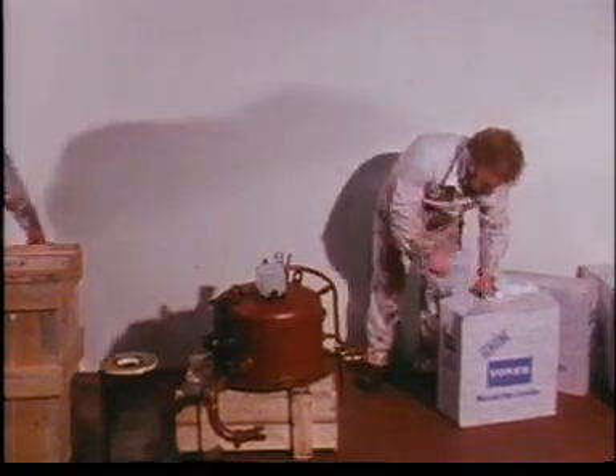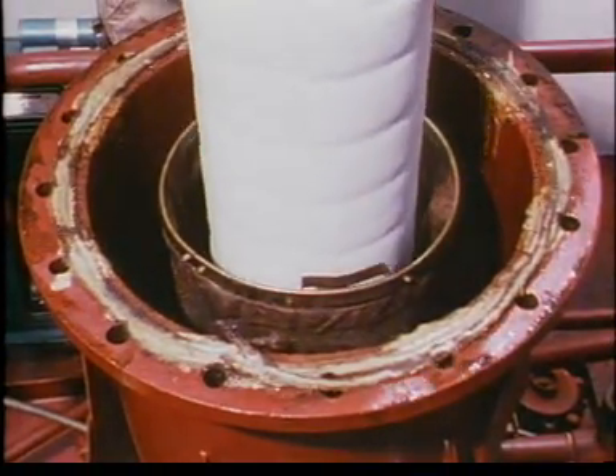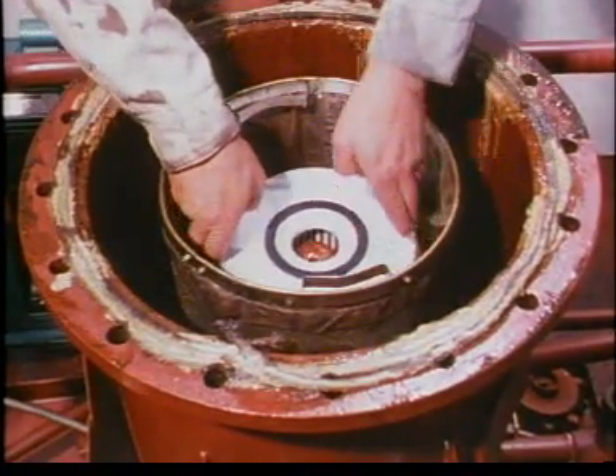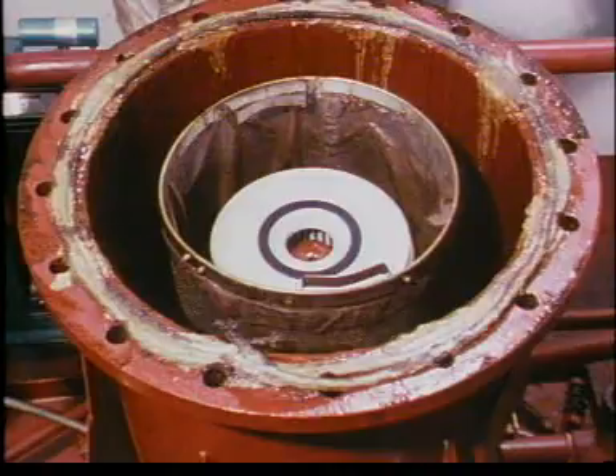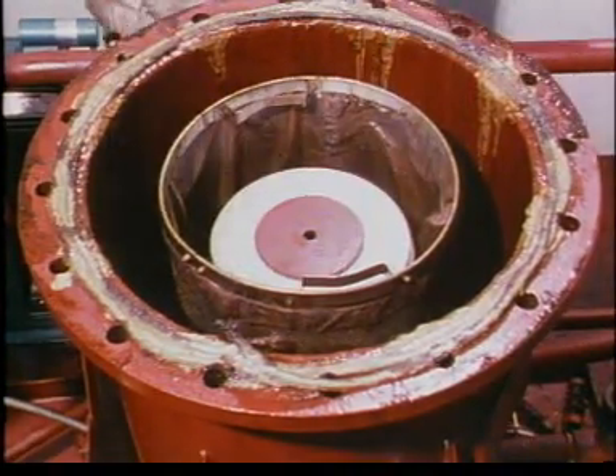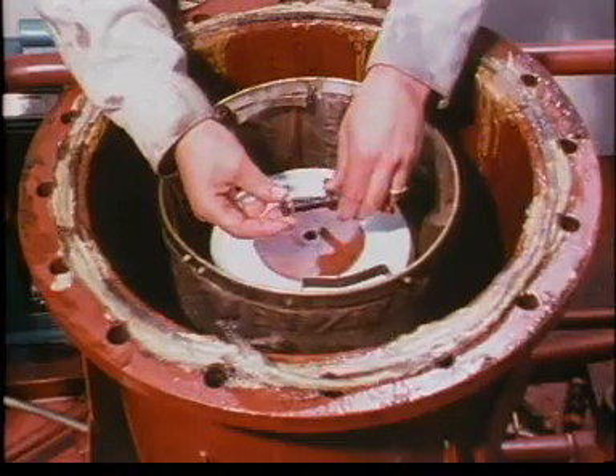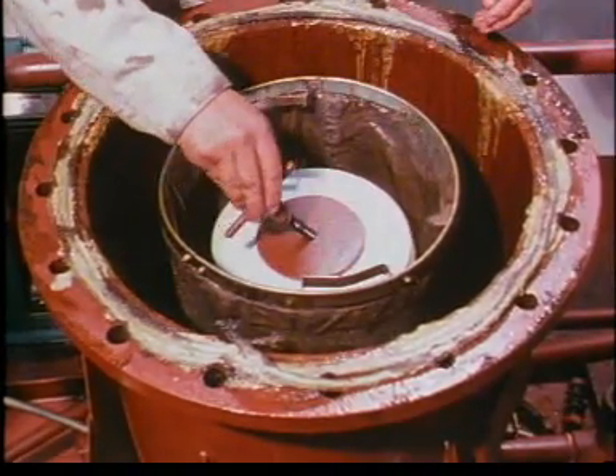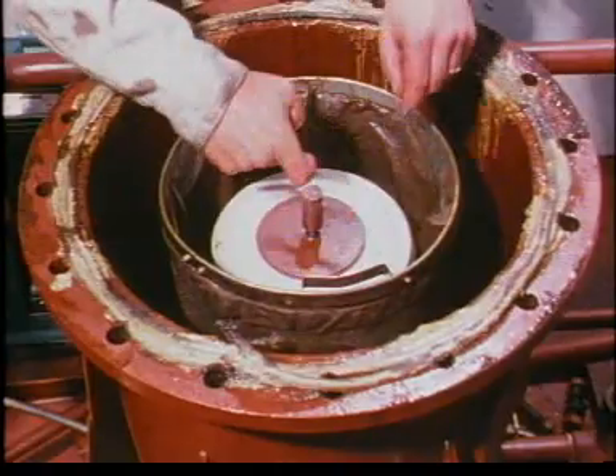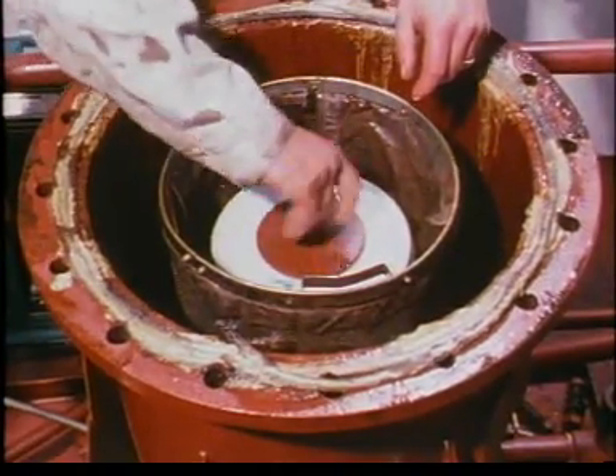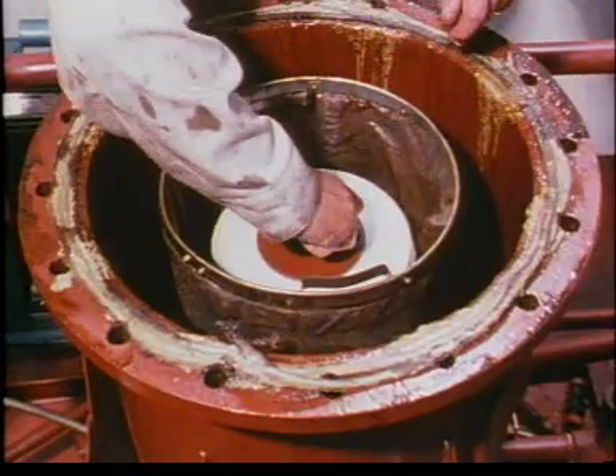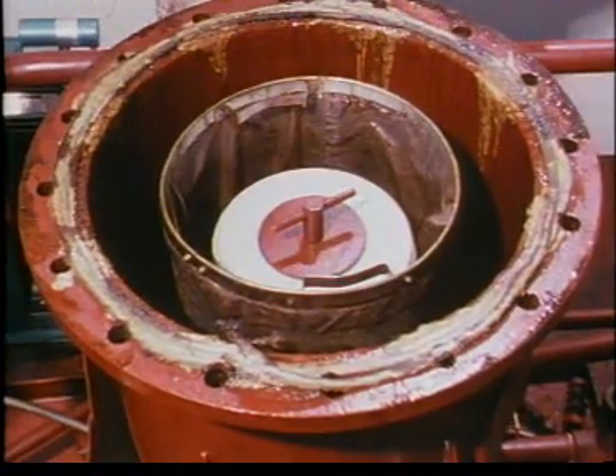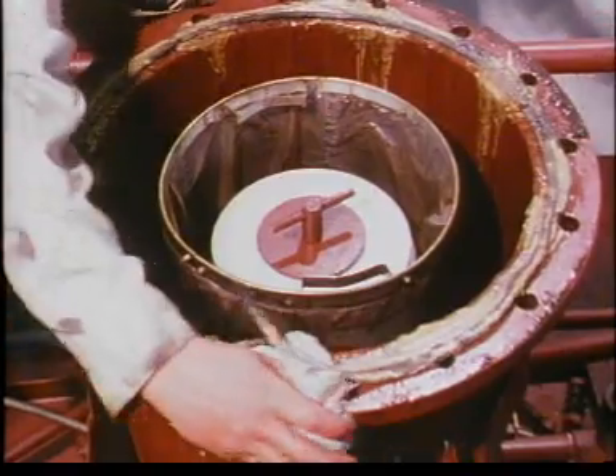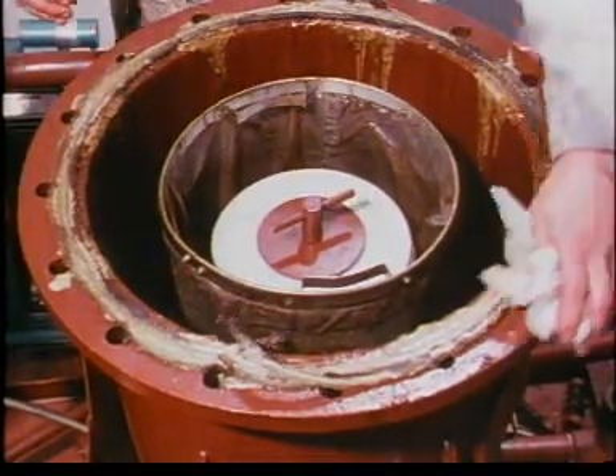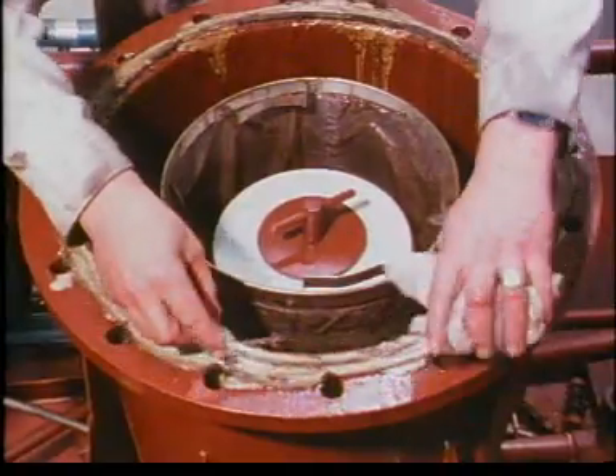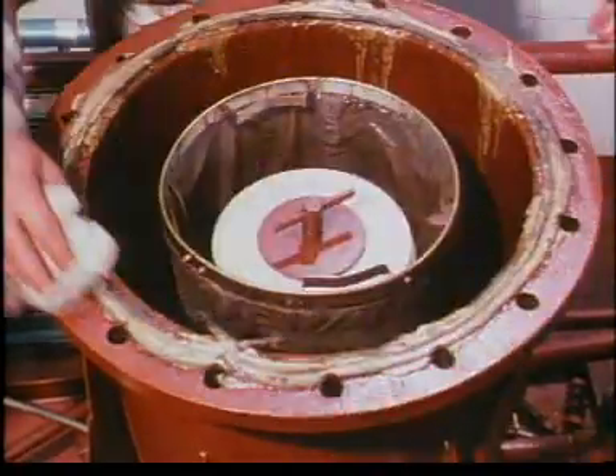When all the dirty elements have been removed, new elements may be fitted and the coalescer reassembled. Make sure that the correct coalescer elements are fitted as recommended by the manufacturer. Be careful not to omit this washer, since if you do, the element will not be properly sealed. It is very important when reassembling to see that the faces are clean and correctly jointed so that there are no leaks after completing the reassembly.